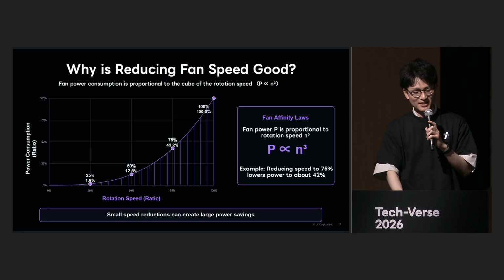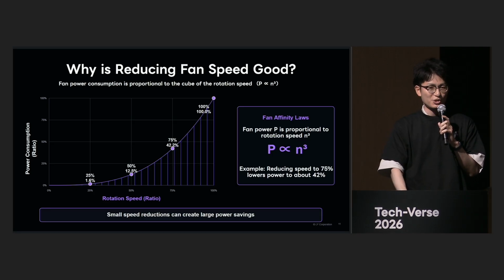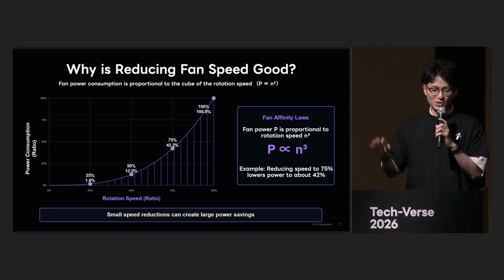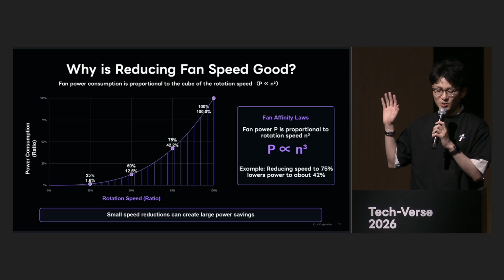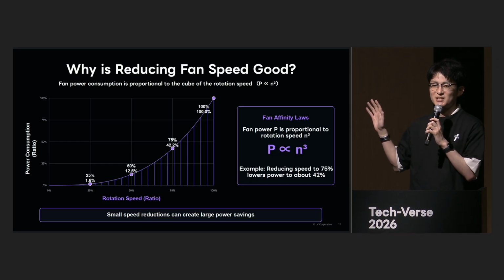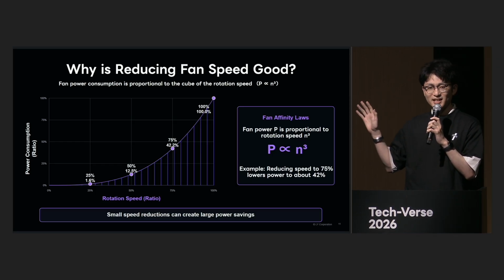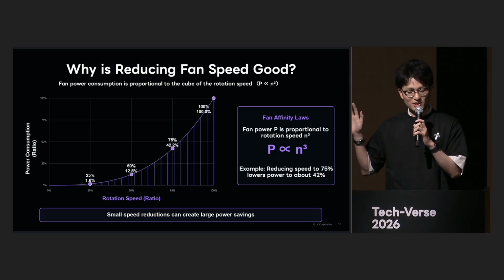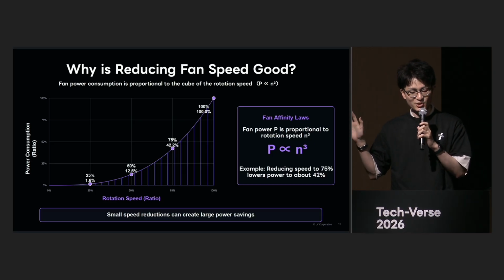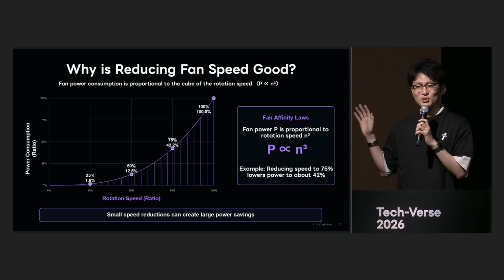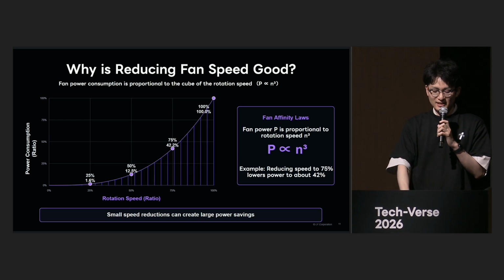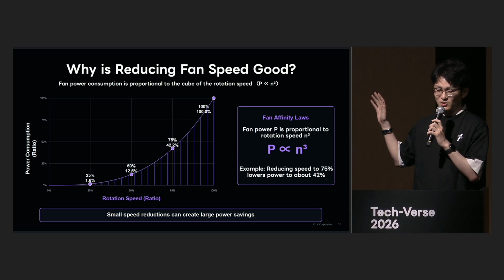This involves a physical law called the cube law, as shown in this equation. The power consumption of the air conditioner's fan is proportional to the cube of the rotational speed n. In other words, if you lower this rotational speed n even slightly, the power consumption P dramatically decreases.